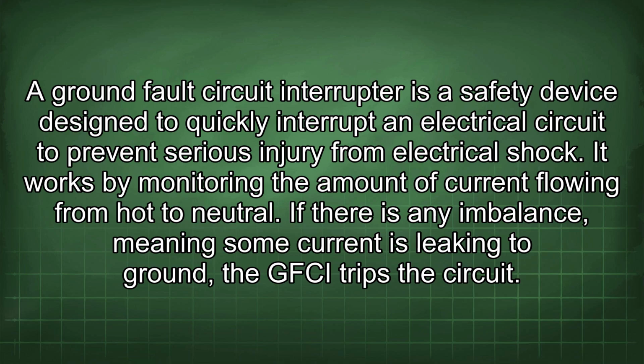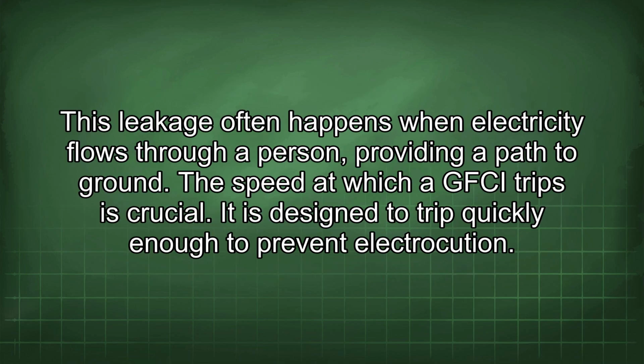A ground fault circuit interrupter is a safety device designed to quickly interrupt an electrical circuit to prevent serious injury from electrical shock. It works by monitoring the amount of current flowing from hot to neutral. If there is any imbalance, meaning some current is leaking to ground, the GFCI trips the circuit. This leakage often happens when electricity flows through a person, providing a path to ground.